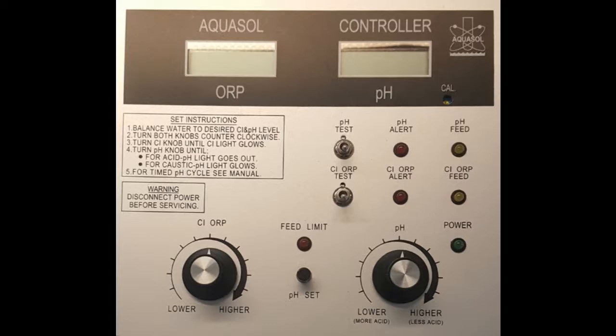And then does it automatically clear on its own? No. It only automatically clears with the ORP. So to get the pH out of alert, you unplug the unit, plug it back in, and do a power cycle. Okay. Now, isn't there like a 2-minute delay or something? On the pH, there's a 1 minute. If it's below the threshold, you have 1 minute to get it back up over that threshold before it actually comes back on. So say a customer was to manually add some acid to the pool, and some of that acid was to go down the main drain or the skimmer line, and the pH drops for a short period of time. It's delaying going into alert, but it isn't going to come back out of alert on its own. No, it's not going to come back out of alert on its own. If you add it to the main drain or the skimmer that quickly, it should shoot right down and go right into alert. Right. Okay.